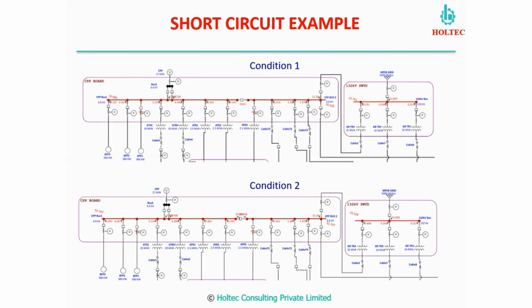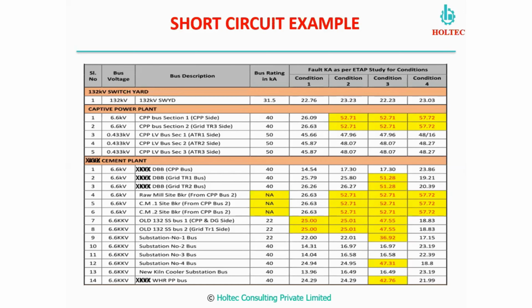After the SLD, this is a tabular form of the study results, where we have done it for 4 different conditions, and we found against the rating what the fault levels are in various operating conditions. In that way, we can tell you which condition is safe and which condition is not safe. This will help you while you operate the plant.